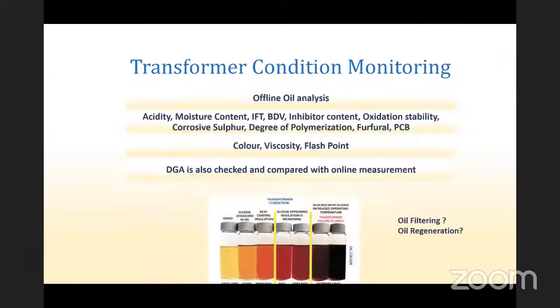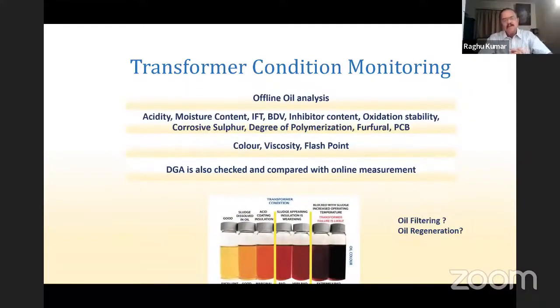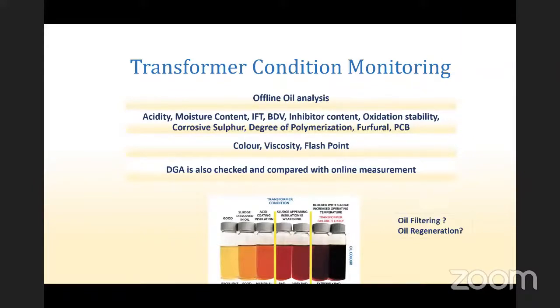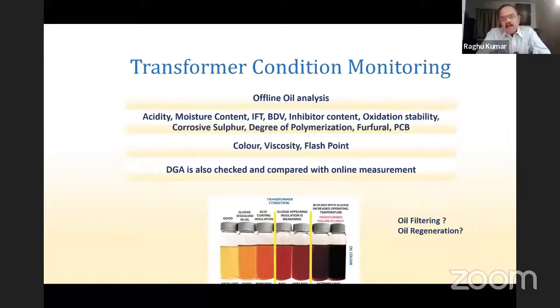Next, we do some offline monitoring. Offline analysis is required to find out the physical conditions of the oil, like acidity, moisture, interfacial tension, breakdown voltage, inhibitor content, oxidation stability, corrosive sulfur, degree of polymerization, furfural, PCB, etc. Each is a huge subject. Corrosive sulfur is a big issue, which is created by a substance called DBDS. In the late 90s and early 2000s, when the transformer requirement was very high, the oil was passivated with DBDS, which started giving problems of copper sulfide formation and rusting.